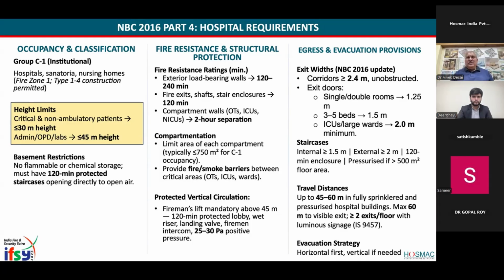Travel distance has always been a debatable subject. But the NBC allows about 45 to 60 meters in fully sprinklered, pressurized hospital buildings. Okay, maximum is 60, but try not to keep it at 60. 45 is what one should look at. In fact, many towns insist on 30 meters. So try and keep it at 45 at least. 60 is allowed, though. Okay.